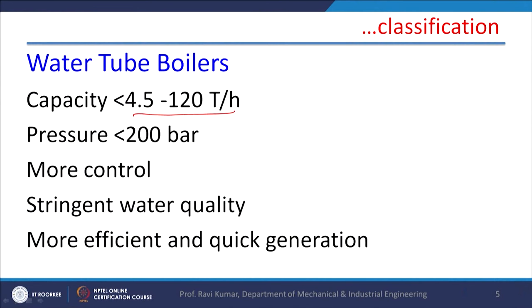Normally, high pressure boilers are water tube boilers. The benefit of a fire tube boiler is that because there is a large pool of steam, if there is a fluctuation in demand this demand can be met by fire tube boilers. Water tube boilers are also possible for this, but several controls are required. The water tube boiler steam generation capacity ranges from 4.5 to 120 tons per hour, and pressure can go up to 200 bar. More controls are required because water is flowing inside the tube — if there is an obstruction in the flow, an accident may take place.